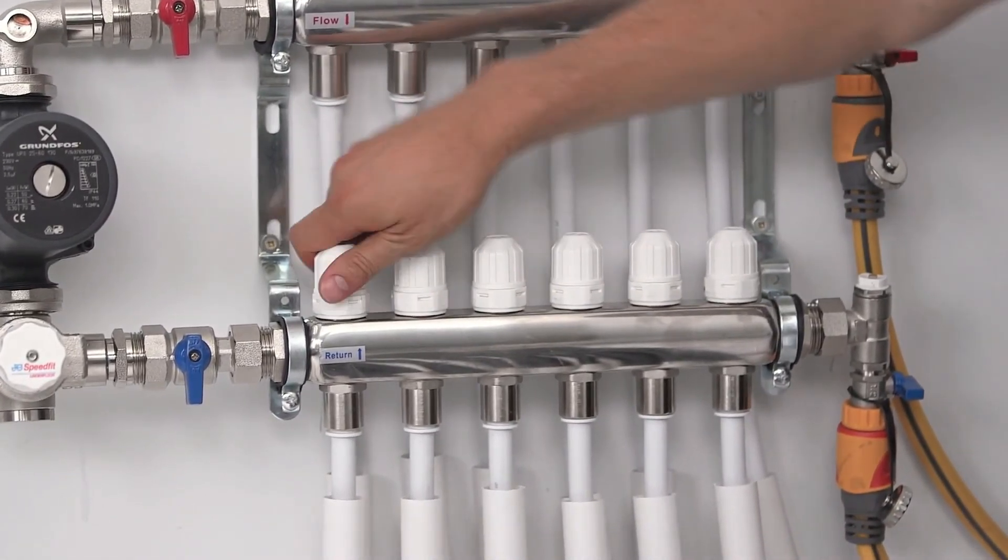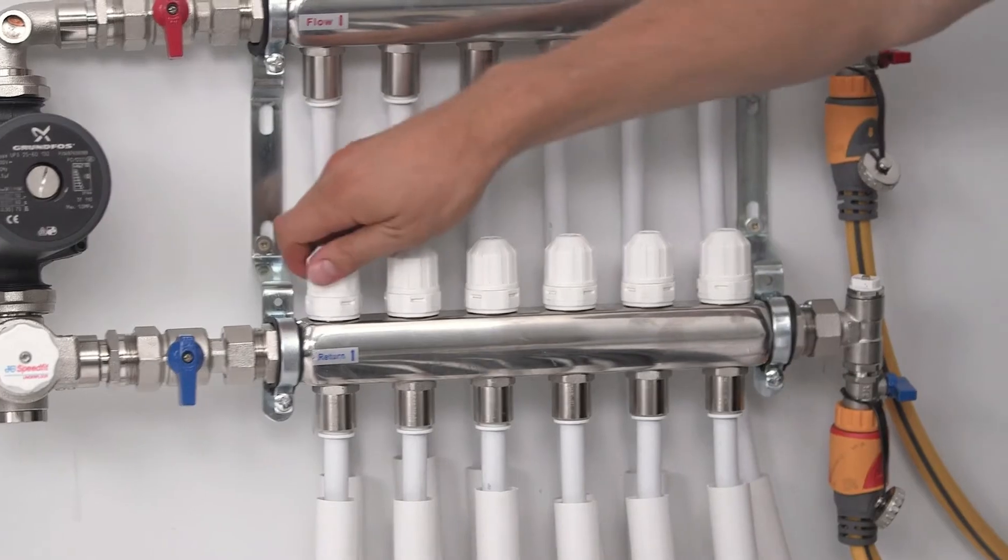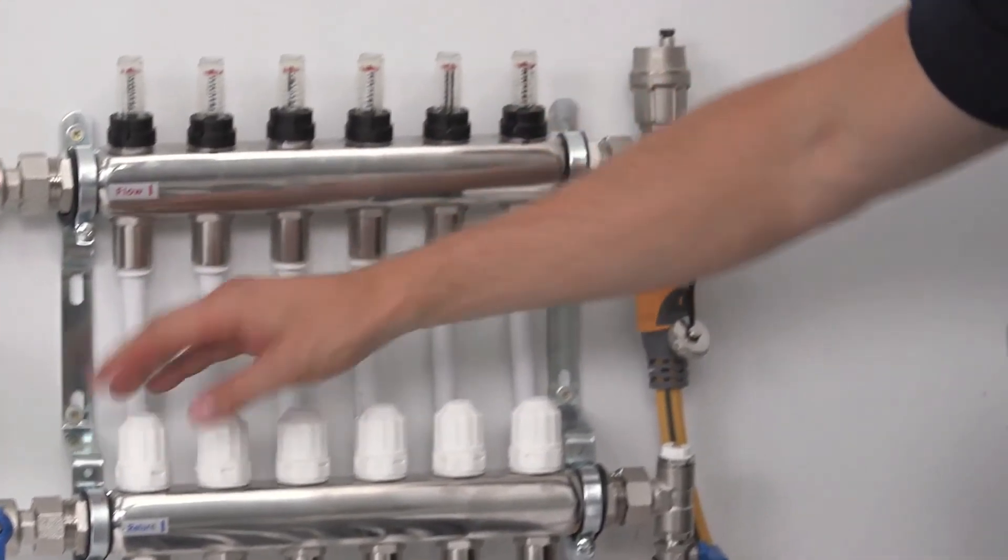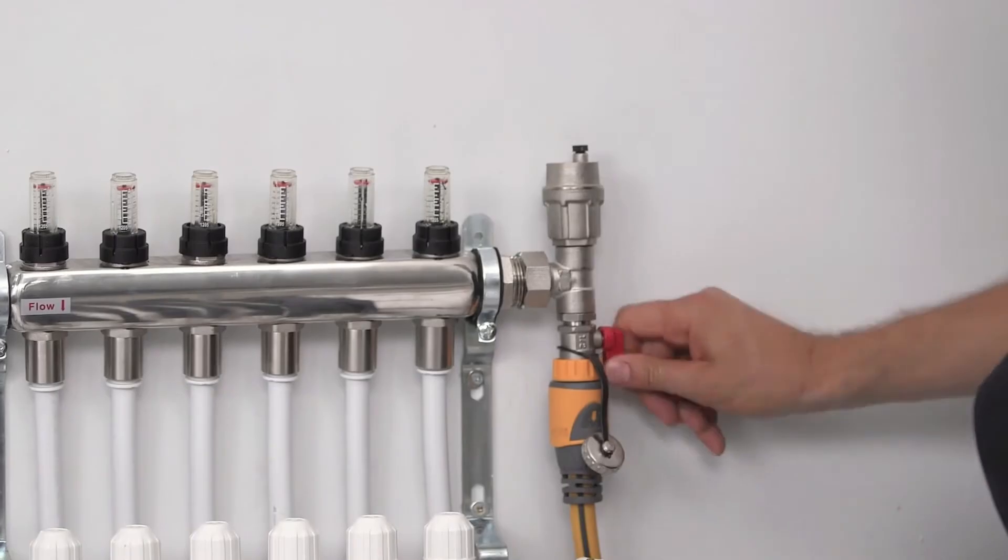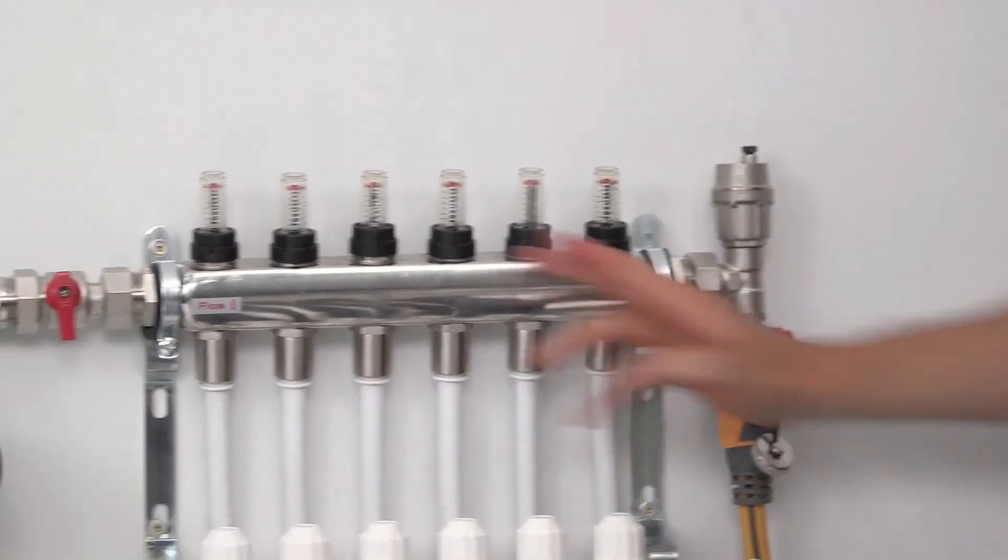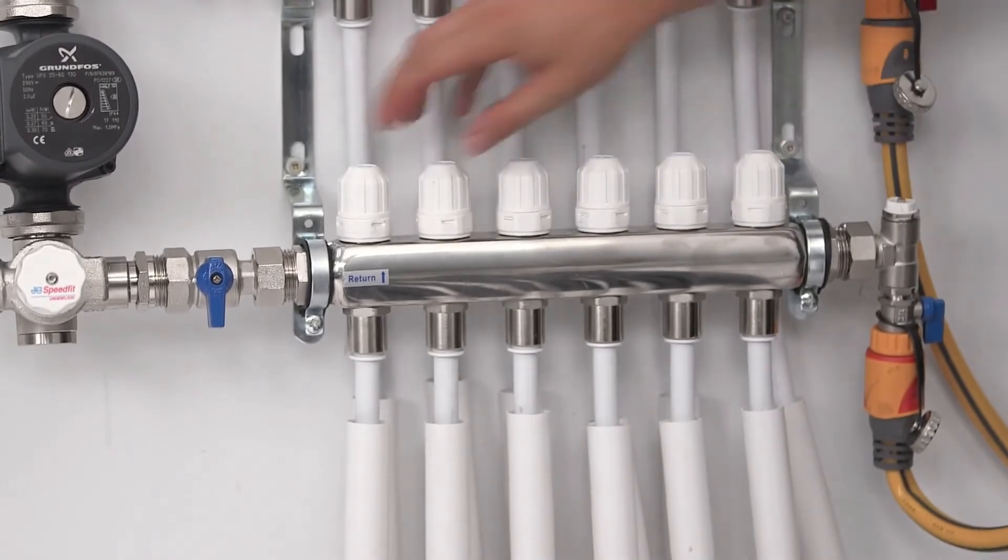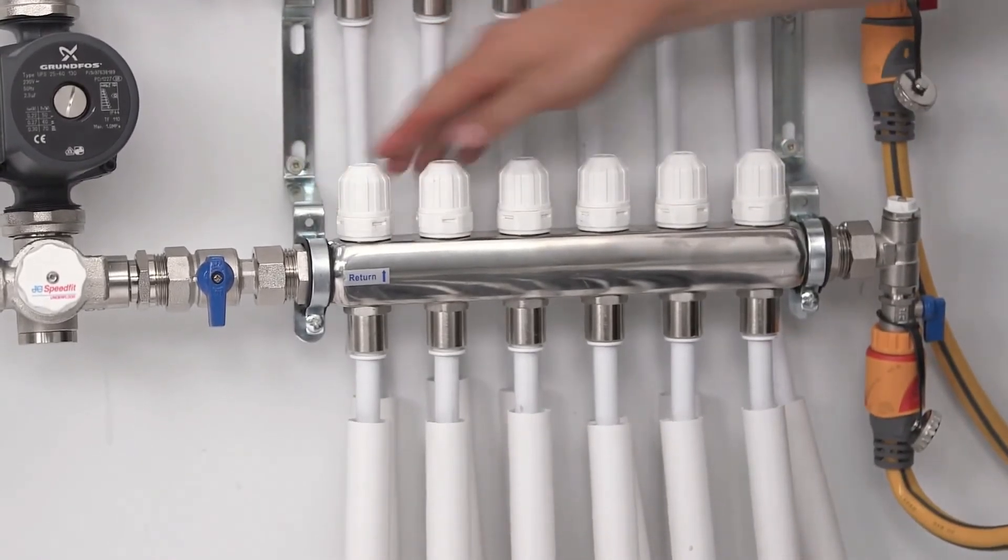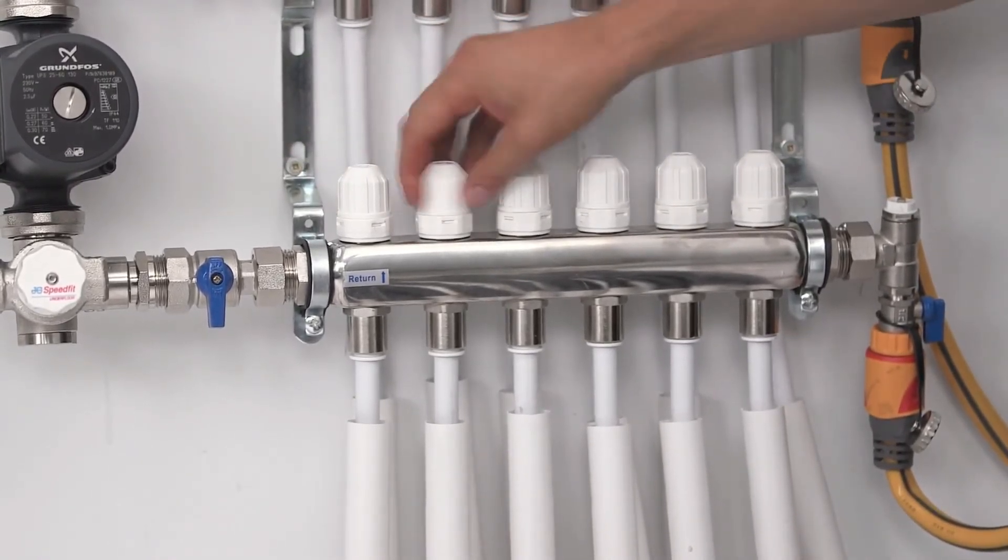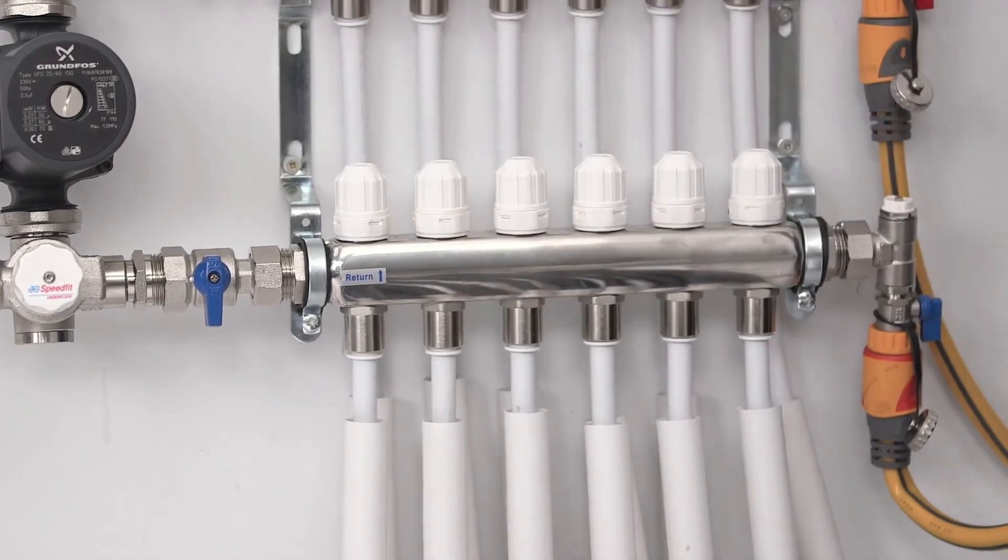Then, starting at the furthest end of the manifold, open only one of the decorators caps. Flush the water around the loop until all the air is purged. Close the cap and open the next circuit. Repeat the process until every circuit is purged.